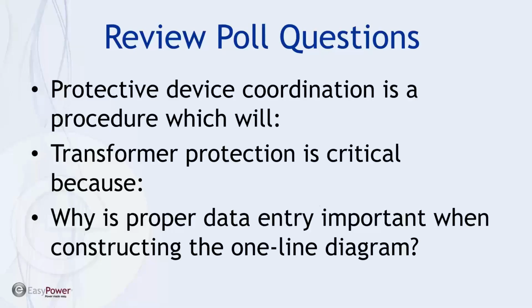So one of the things that's important to remember is that coordination very frequently increases the arc flash exposure on the particular bus. So you don't want to get confused between mitigation and coordination. It's an issue that will come up frequently when we get into arc flash protection. So transformer protection is critical because this one's kind of a throwaway. Yes, let's give this another 10 seconds. So yeah, the correct answer is all the above, and I didn't mean to pull that on you. Probably should have put all the below.